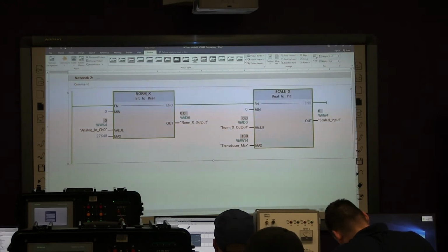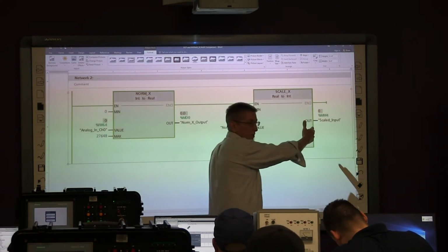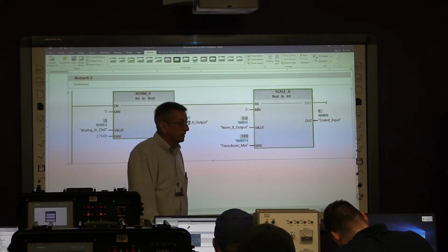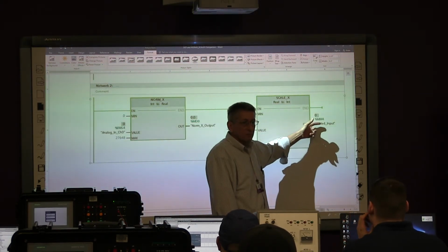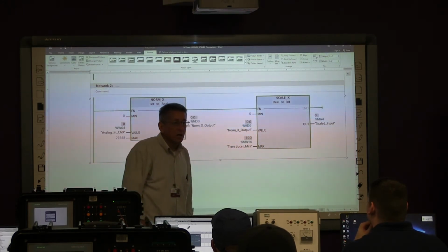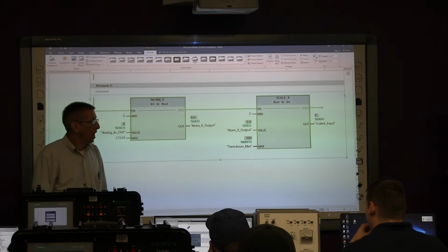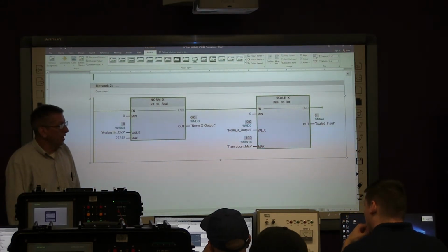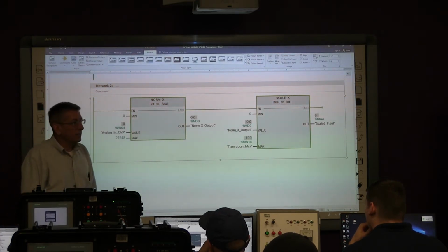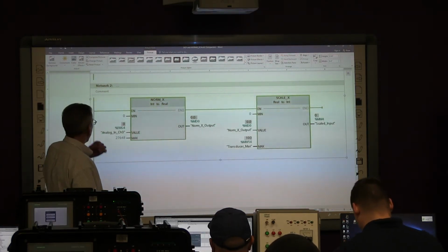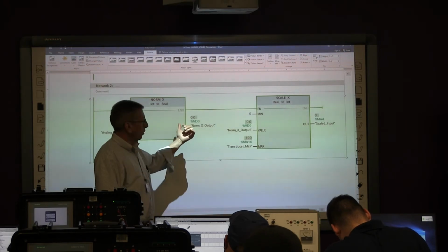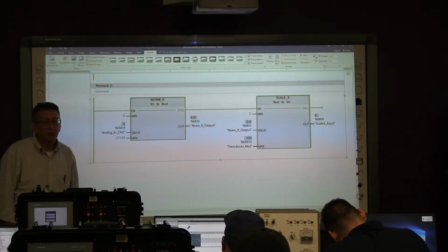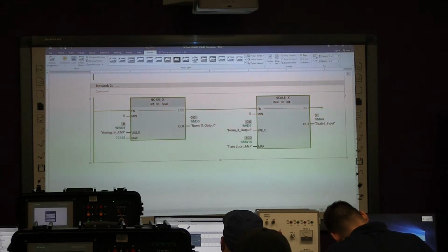That makes sense? Think of it this way, you have to have raw units coming out of here to drive some analog device, because this is the interface going directly to your analog output module. We're going to have to do the formula where we balance it to 0 and balance the scale in order to have the real numbers for the raw unit. But a test question might say something like, if we have 75 PSI going into this thing, what's the output of the NormX instruction going to be? So 75%, it would be 0.75.